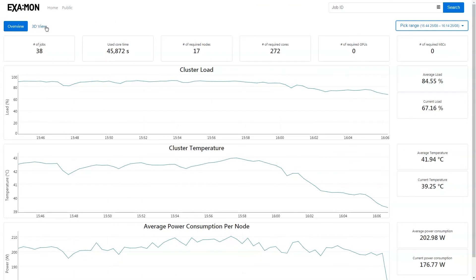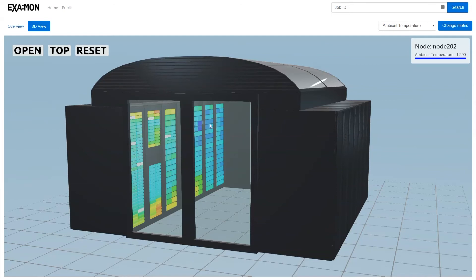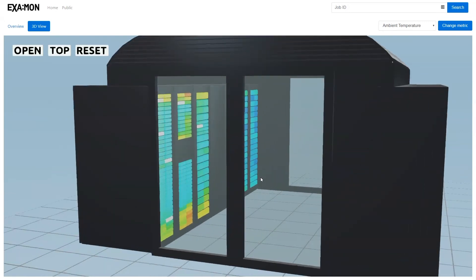Now let's move to the coolest part of the app: the 3D model. Once the model is loaded we can see a 3D model of the Galileo cluster itself. The nodes are color coded — right now it shows ambient temperature, which is the temperature of air flowing into the node. Blue is around 12 degrees, ranging to red, topping at around 28. We can navigate the model using pan, zoom, or rotation.